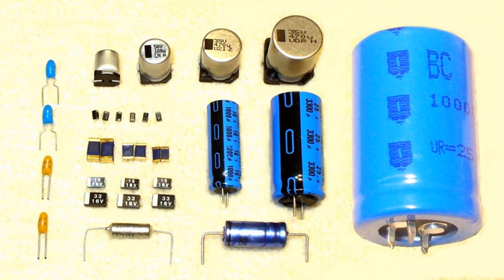Billions of tested capacitor unit hours would be needed to establish failure rates in the very low level range which are required today to ensure the production of large quantities of components without failures. This requires about 1 million units over a long time period, which means a large staff and considerable financing. The tested failure rates are often complemented with figures resulting from feedback from the field from big users concerning failed components, the field failure rate, which mostly results in a lower failure rate than tested.